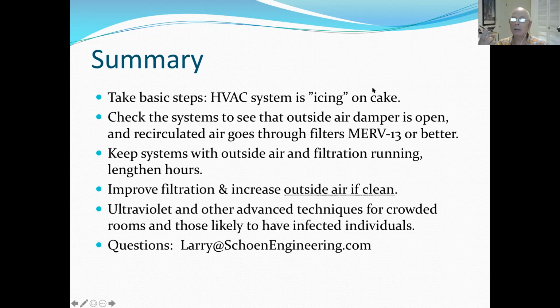Is your outside air damper open? Do you have a MERV filter in place? How much air are you delivering? Have you measured that with a balancing contractor, or do you have your own means for doing it? ASHRAE recommends measuring it at least once every 5 years. Is air flowing to every room? Make sure nothing's closed off in terms of a damper. There's a short checklist.